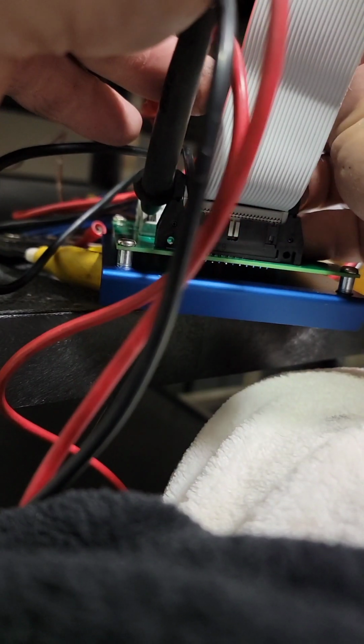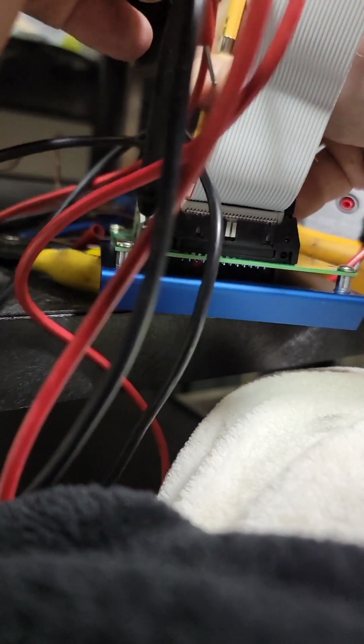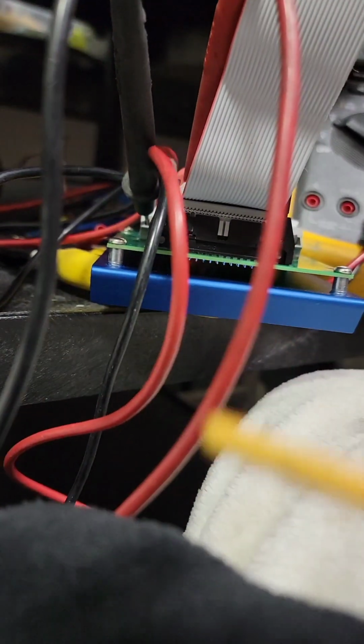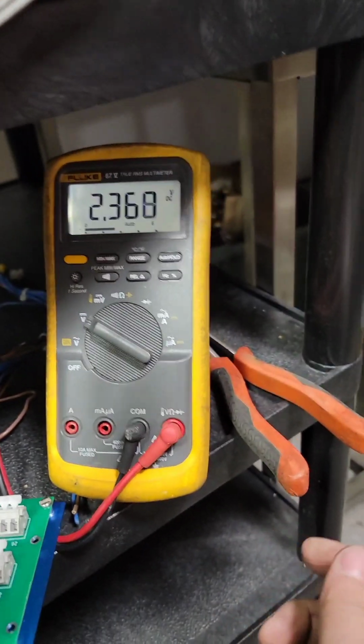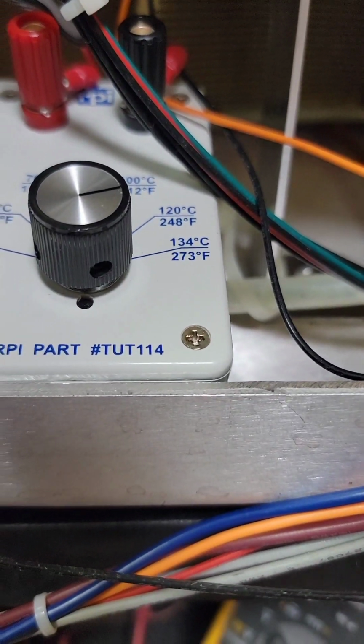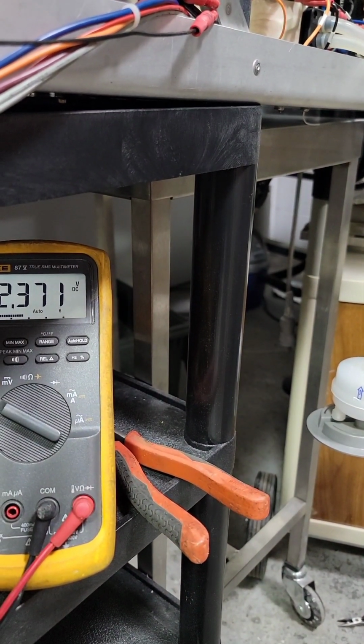All right, we'll move our positive lead from 4 back to 7. Now, even though I'm going backwards, it doesn't make a difference on this. I like to go through everything a second time on each lead to verify that none of my adjustments have caused anything else to go out of whack. So let's remember now. For the 273 Fahrenheit temperature setting, we want to be at 2.385, and that is pot 4, this bottom right one here. So I'm going to go clockwise to go up.